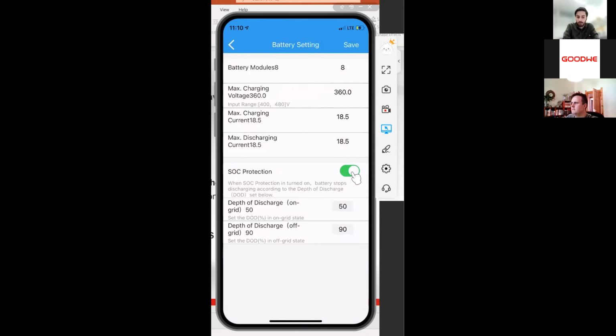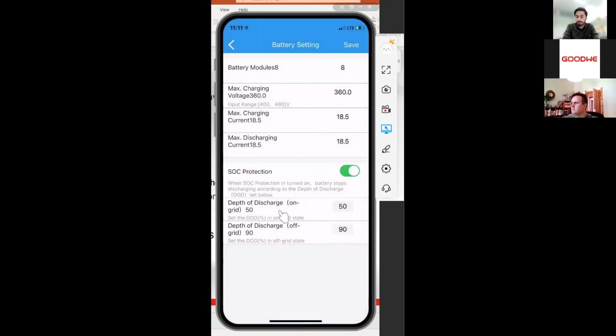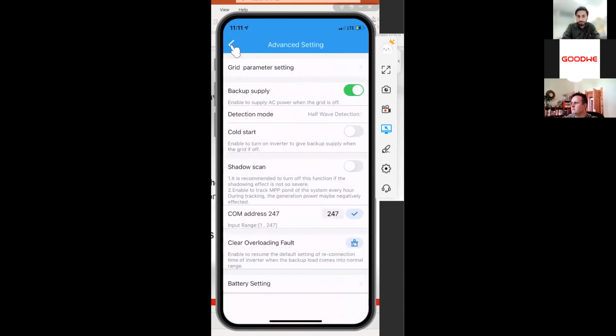Here you can set the state of charge protection. So here you can set some different depths of discharge for different purposes. So you can have, when it's connected to grid, the battery can use 50% of the capacity, and when it's maybe for backup, then you have 50% over, and then it can discharge down to 90%. So you can use 90% of the total charge. So here you can change this depending on what you require. When you're done, you always click on save, and then you can return. Yes, and when you're done, it always needs to restart to apply the settings.